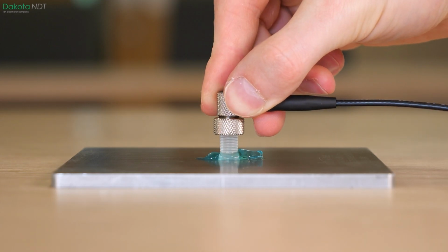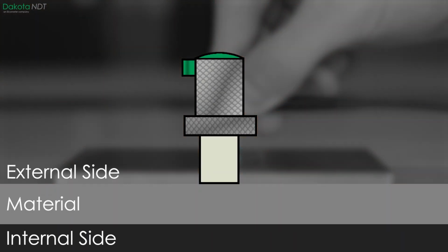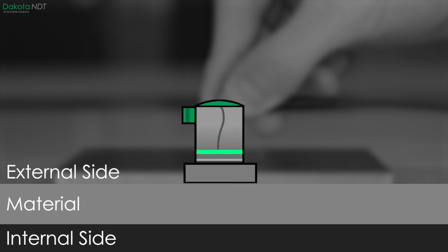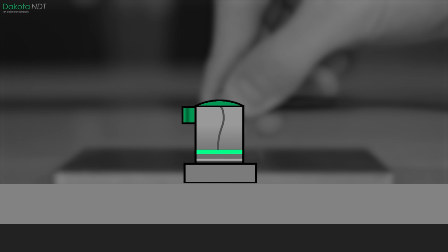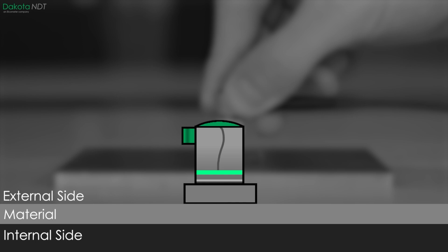Single element transducers consist of a piezoelectric crystal which emits an ultrasonic pulse when triggered by a voltage. This energy pulse travels from the transducer and into the material, aided by ultrasonic couplant. It then hits the back wall of the material and echoes back towards the crystal, where it is then detected. The gauge then uses the speed of the pulse and the time taken between the pulse being emitted and the echo being detected to calculate the thickness of the material.